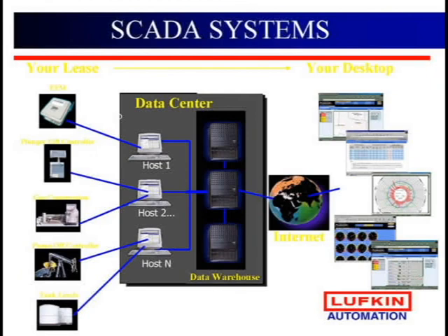So how these all work is we again bring the data back in from whatever you have at a well. You can go into full networks, you can go into a simple computer system, you can take it up through the internet to where you could have just a client on your computer looking all the way back at that well of the data. So every bit of data that's in these controllers is available through these host software packages. The only thing we won't let you change is the radio address. Because if you change that in the computer and you get it wrong, now you're going to have to drive to the well and change it locally, or you'll never know what you're talking to.